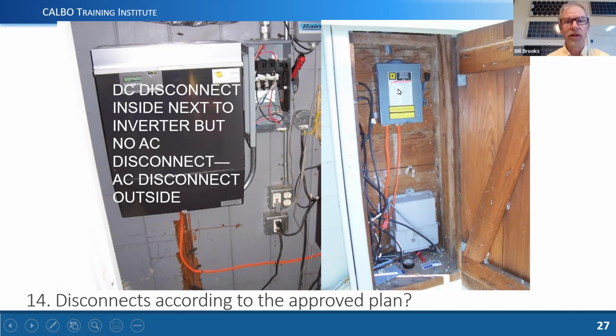And so the problem with that, and the reason that the code in general doesn't allow that, is that, say you're working on this inverter inside the utility room, you've turned this switch off. It would be advisable to lock the switch off in the open position. That's why this thing has a tab right here. But if you turned it off and you didn't think about it, the homeowner could come home from work at 4 o'clock or whatever, they come home early, they want to talk to you about something, and they see this door open on the side of their house, and they go, oh, those stupid kids from the neighborhood, they've turned my system off again. They come over here and turn it back on again, not knowing that you're on the other end of the wire trying to reinstall the AC wiring into the unit, and you get French fried.